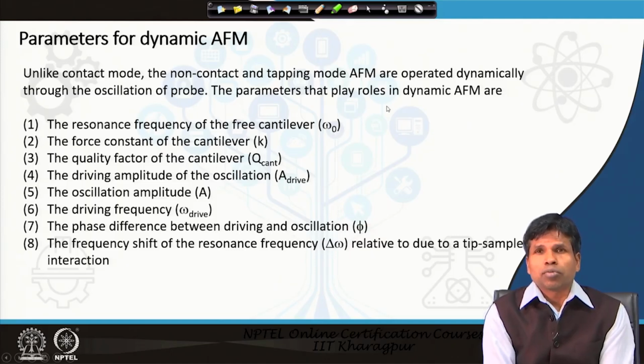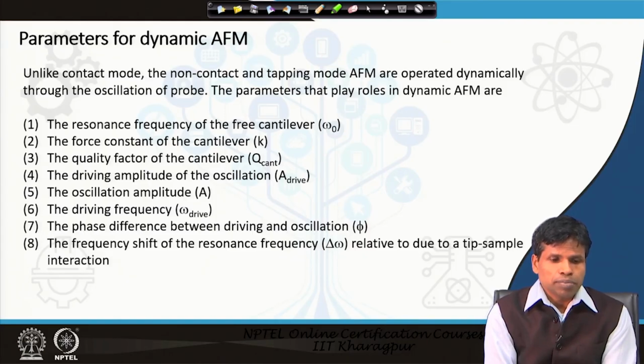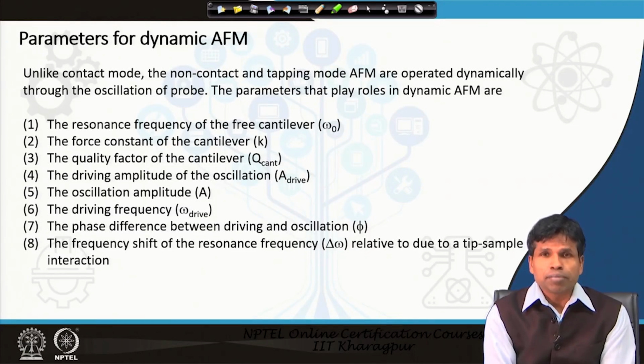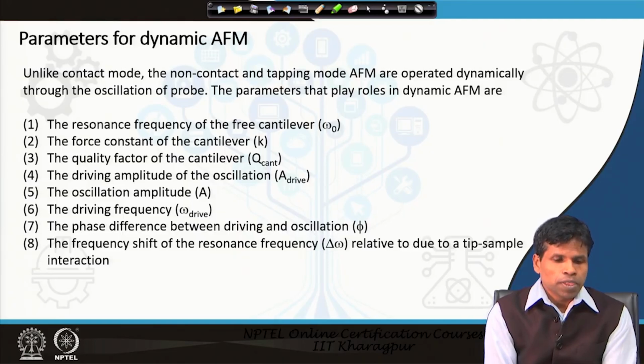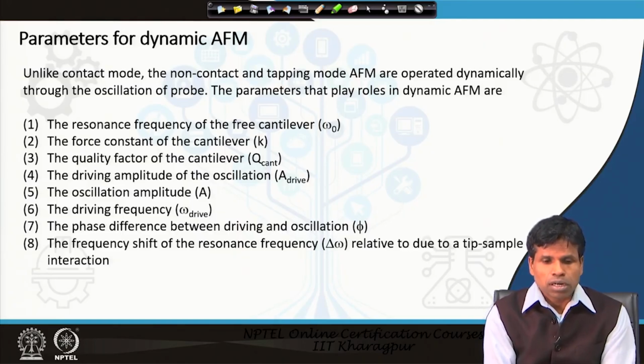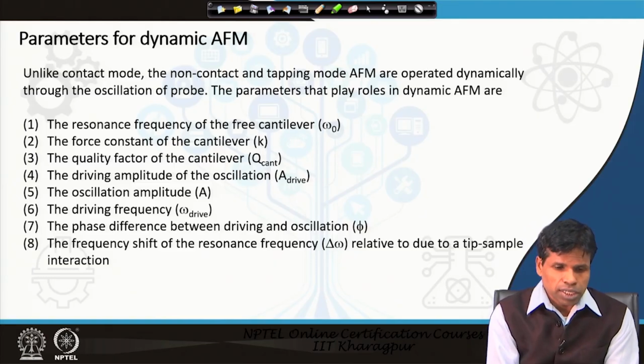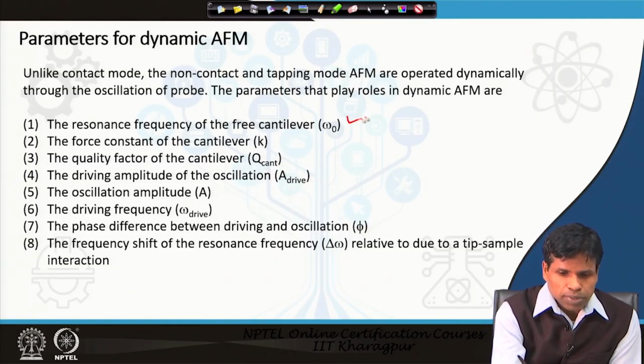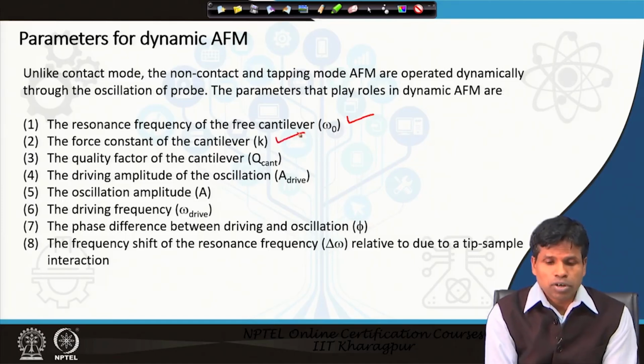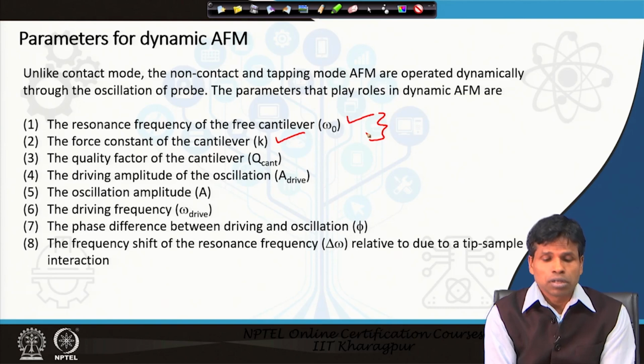The contact mode of measurement goes with static AFM. If we talk about the parameters involved in dynamic atomic force microscopy, this dynamic mode of AFM is used in non-contact mode and tapping mode of AFM, and this dynamic mode of operation involves several parameters. These include the resonance frequency and the force constant of the cantilever; these two parameters are related to the cantilever.